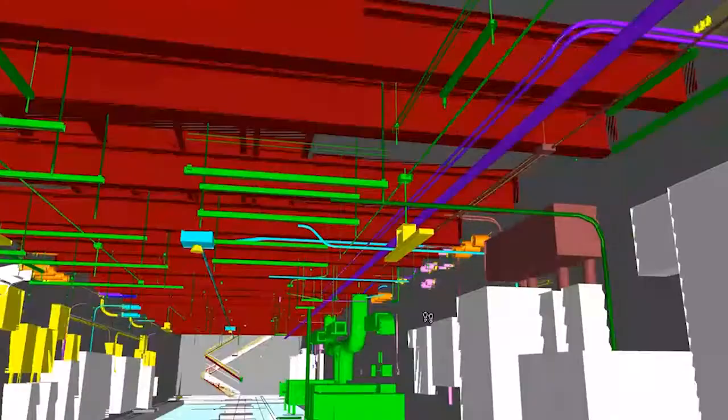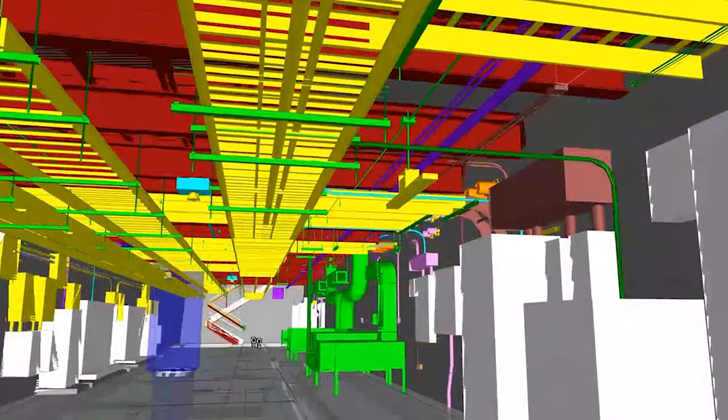And then once we do that, we can export it out into Navisworks, and you'll see a 3D representation of it. Once that's all pulled together, it's just a matter of how much content you want and what you want to extract out. The drafter can immediately fire in there and start drawing a conduit, getting everything you need, getting it to the real world dimensions, and then basically putting it on an install drawing and getting it over to the prefab department.